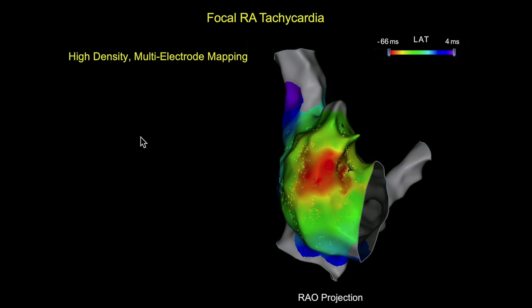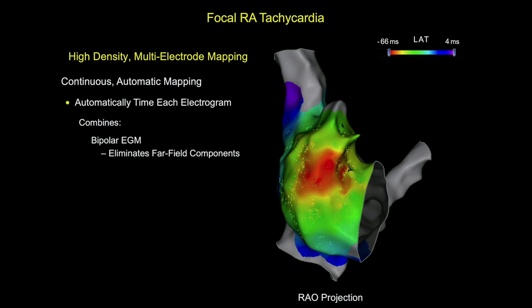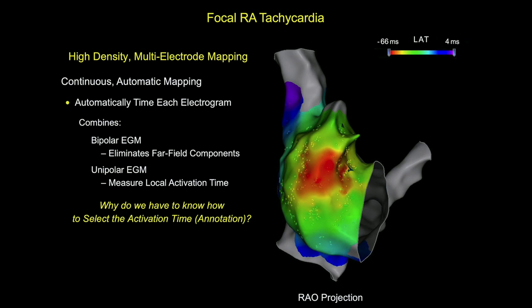Today we have multiple systems that allow high-density multi-electrode mapping. These systems allow us to move the catheter around the chamber and continuously acquire mapping data. In order to do that, these systems have to automatically time each electrogram. They do that by combining information from the bipolar electrogram and the unipolar electrogram. The bipolar electrogram is used to eliminate the far-field components of the signal, and the unipolar electrogram is used to measure the local activation time for each electrode. So the question is, if we have automatic, rapid, high-density mapping, why do we have to know how to select the activation time?